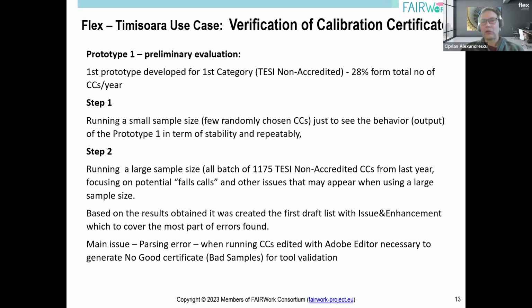The result was according to expectation. This does not mean pass or fail; even where it failed, when you look at the failures, they were expected failures. I'll explain more about this later. In step 2, we ran a large sample size, in fact the whole batch of 1,175 non-accredited certificates from last year. Of course, there were a lot of failures, but most of them were so-called false calls, because there were discrepancies between what was written in our calibration database and the way it was issued by the service provider.